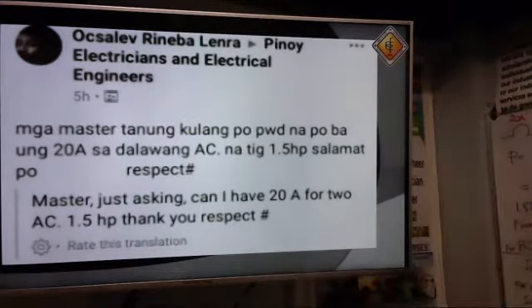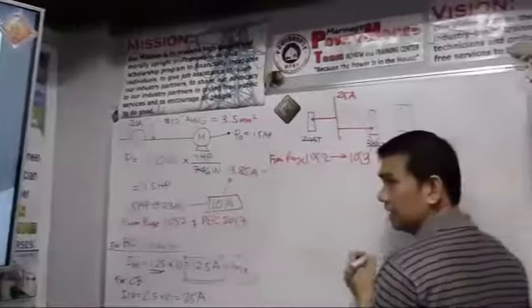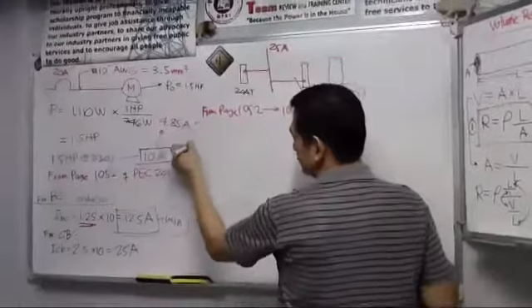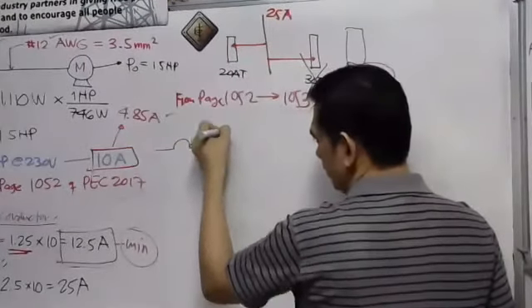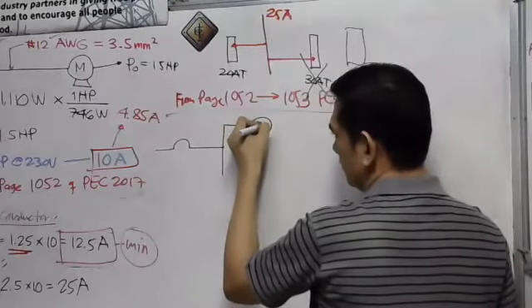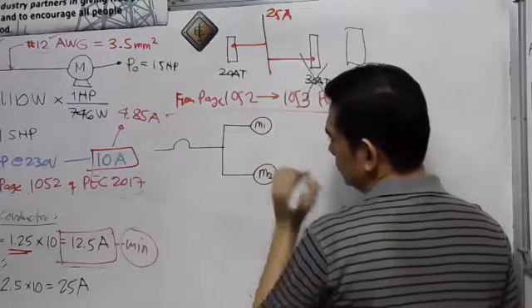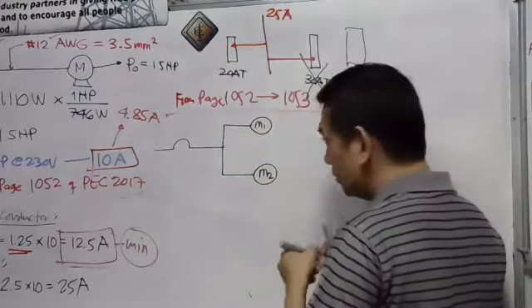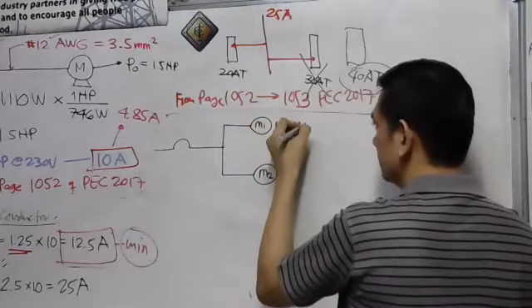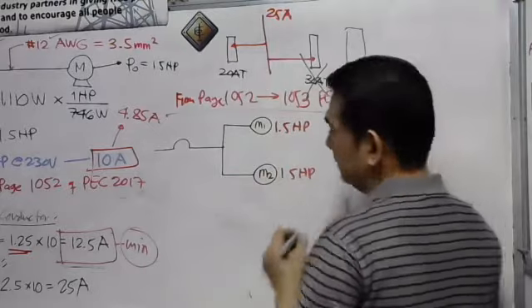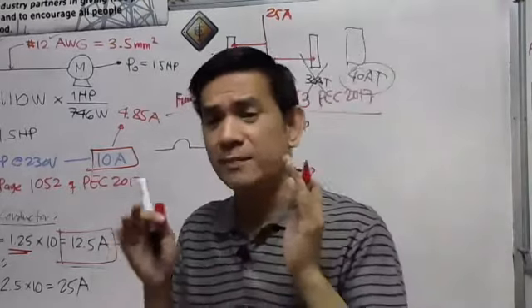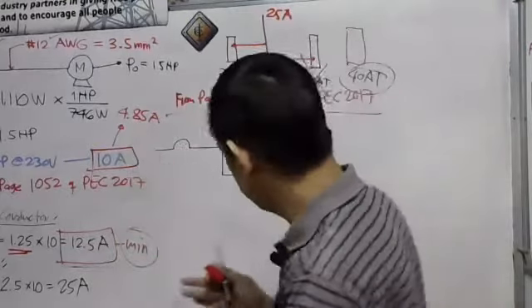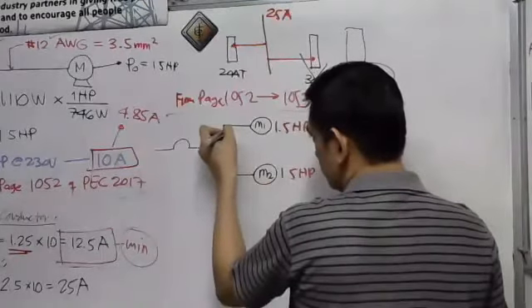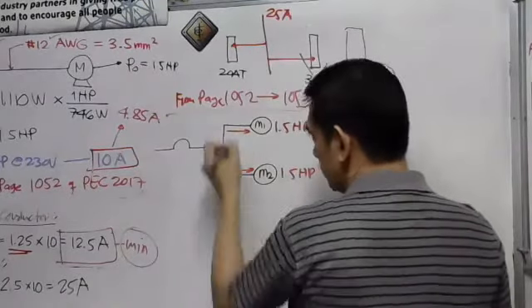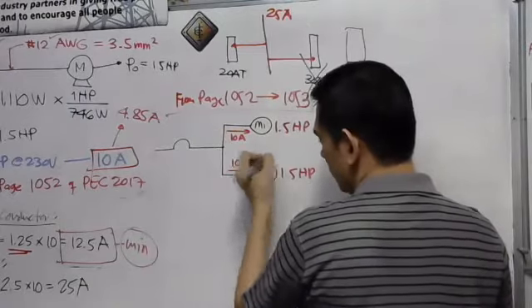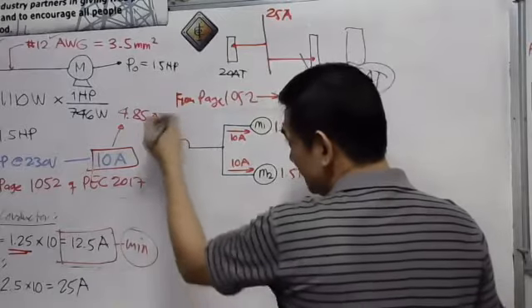Okay, I will discuss here. He's saying he has two motors or air conditioners that are represented by a motor. Motor 1, this is motor 2. You have 1.5 horsepower. Again, from the Philippine Electrical Code, what is the ampacity of 1.5? Okay, let's consider 230 volts. This is 10 ampere from the Philippine Electrical Code. 10 ampere also. But your ampere here is just 20 ampere.